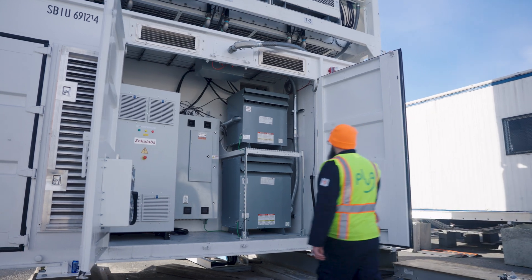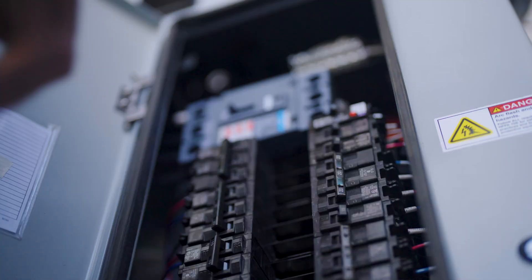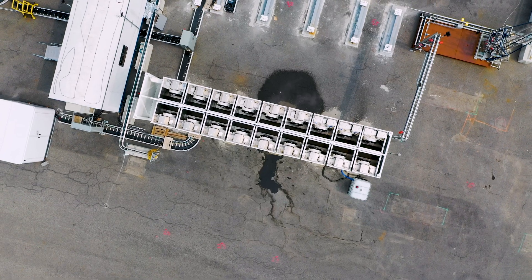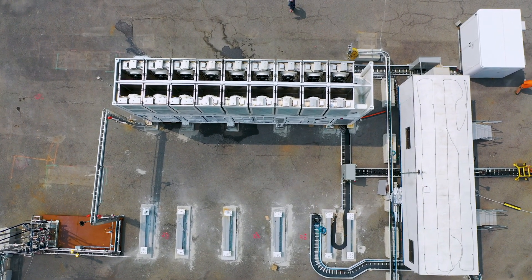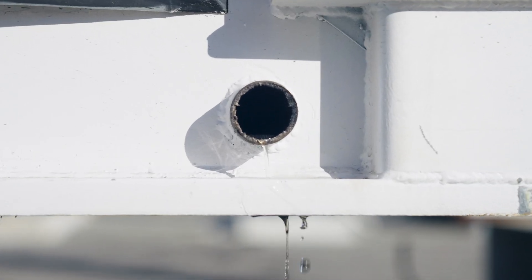In this area are the balance of plant power supplies, which are for controlling the cooling tower, environmental, and safety systems that the fuel cells need to operate. Above that is the cooling tower that sits atop the fuel cell container. The only byproduct of the fuel cell's process is heat and water. Up here you can see the cathode exhaust, which contains warm moist air, and around this corner is the system drain where the byproduct is pure water.